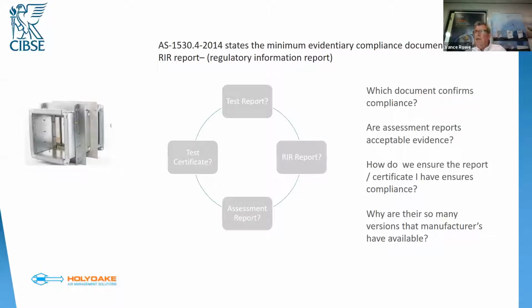So generally the way this works is usually we'll do a section 11 test for a vertical, and we'll do a section 11 test for a horizontal. So we're taking care of the 300 Pascal pressure differential test, and that's for the entirety of the test. Usually we'll do that in a concrete wall or a concrete floor slab, and the reason for that is we want to prove that integrity for 4 hours, which is the maximum that we test here in Australia.